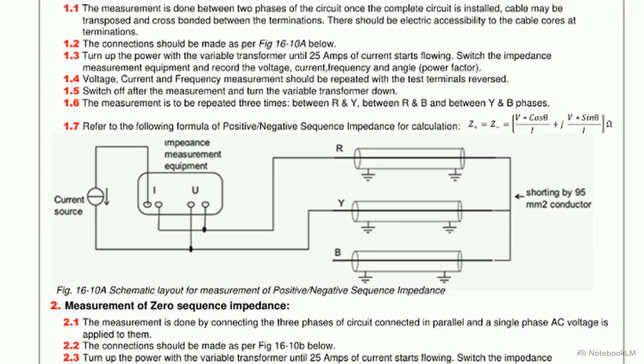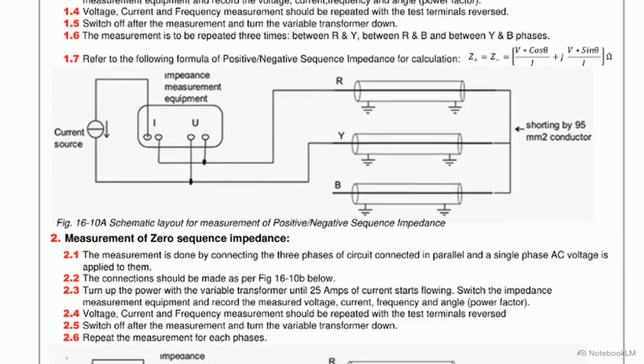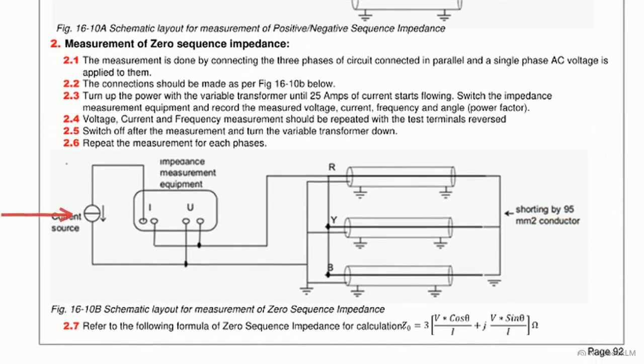Test 13.11 measures sequence-impedance. For positive and negative sequence, measurement occurs between two phases, scaling current from a variable transformer up to 25 amps to record voltage, current, frequency, and angle. For zero sequence, all three phases are connected in parallel and injected with a single-phase AC voltage to calculate Z0.